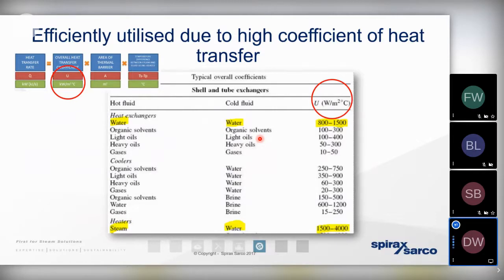And that's one of the reasons why steam to water heat exchangers can be far, far smaller in footprint than water to water heat exchangers. And as most plate heat exchangers that are used on steam systems are gasketed as opposed to welded or brazed, this means we can also manipulate that U value by taking the heat exchanger apart for cleaning and removing any scale or debris that can inhibit the rate of heat transfer.